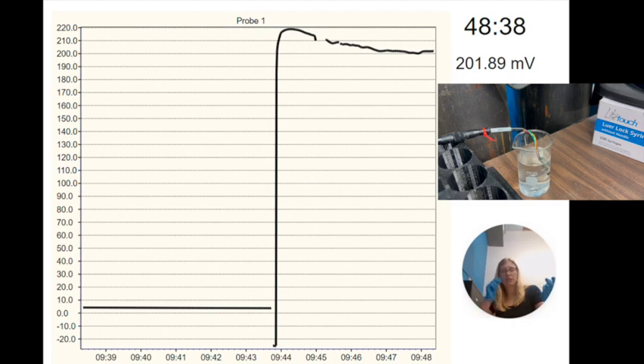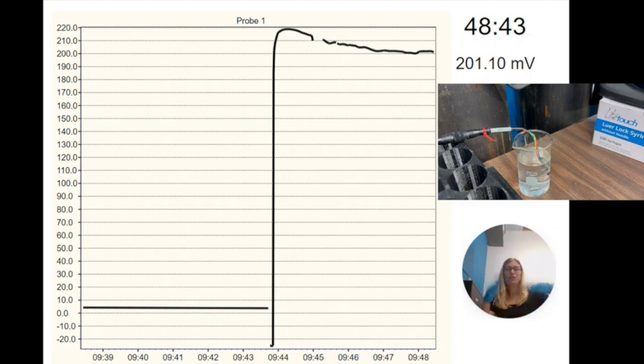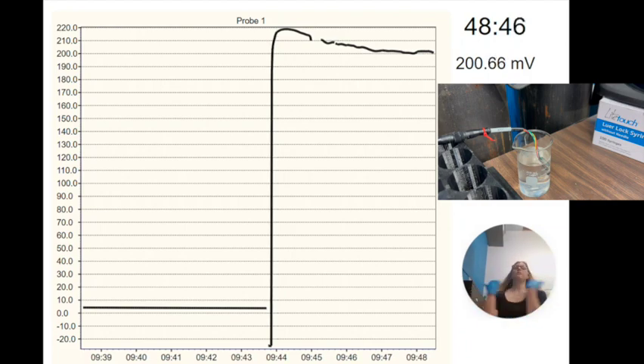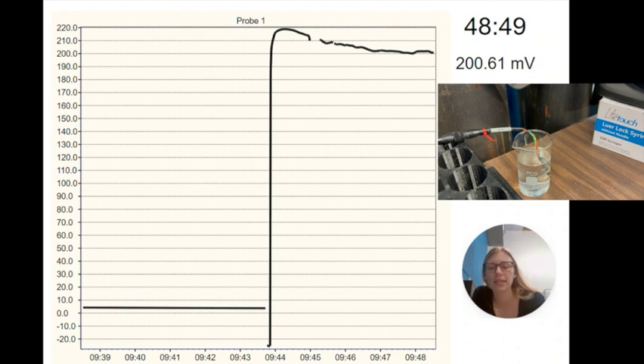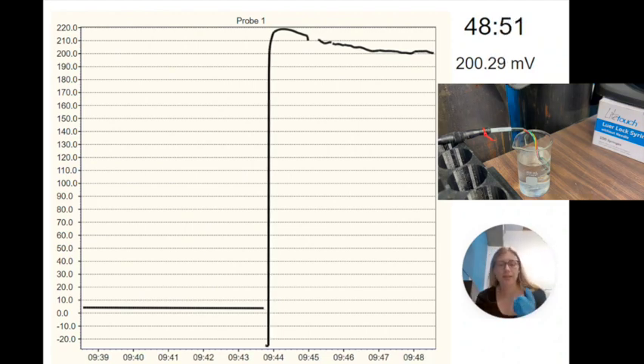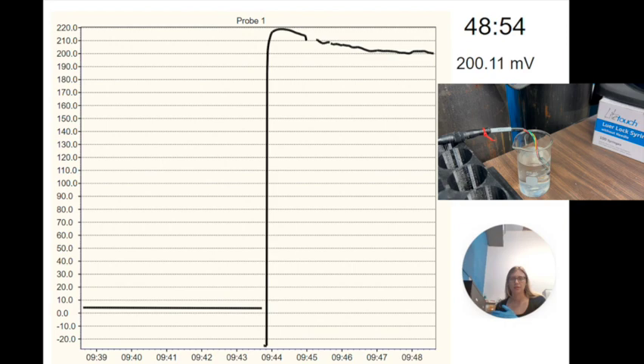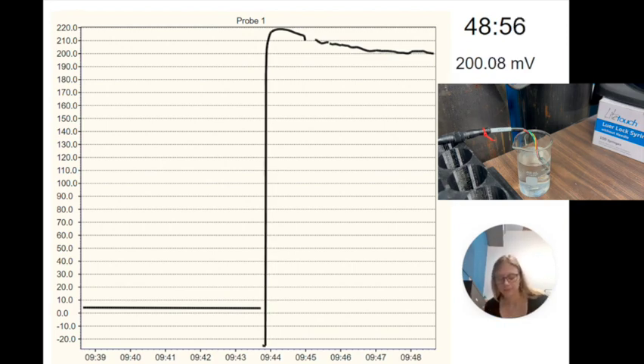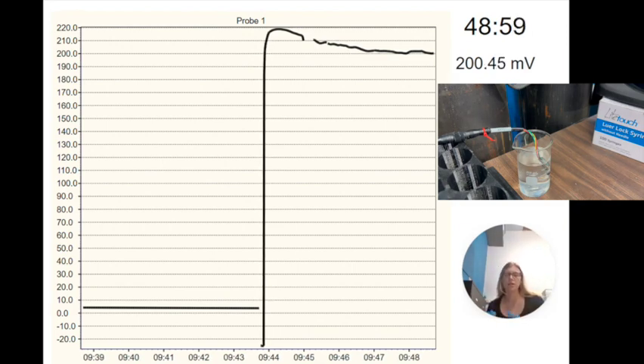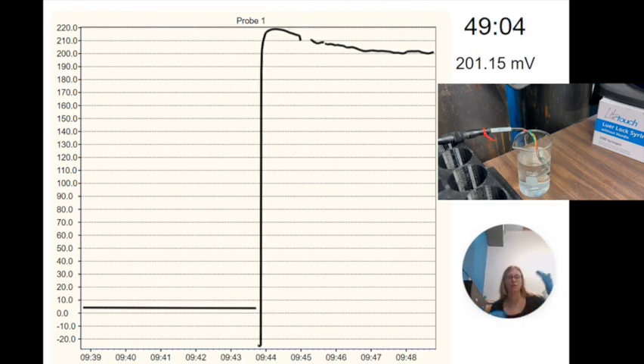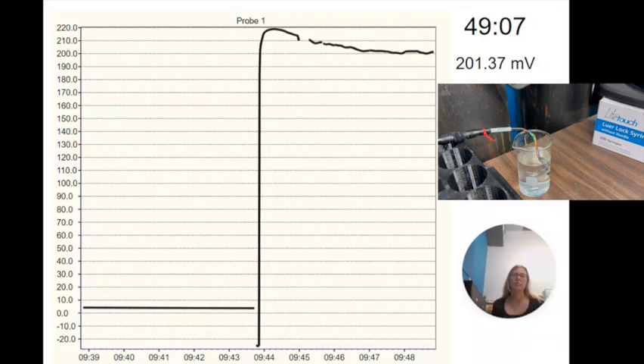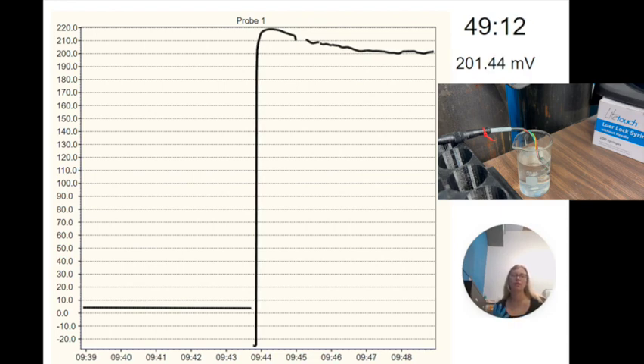So here, this one is reading 201 millivolts, and it's quite jumpy. It also has a few breaks in the readings because it's not making a proper connection with the data logger. Some other things to look out for with electronics are large spikes and jumps of larger than 3 millivolts. This would be an example of an unstable output, and it wouldn't be a reliable offset measurement, even under recovery.